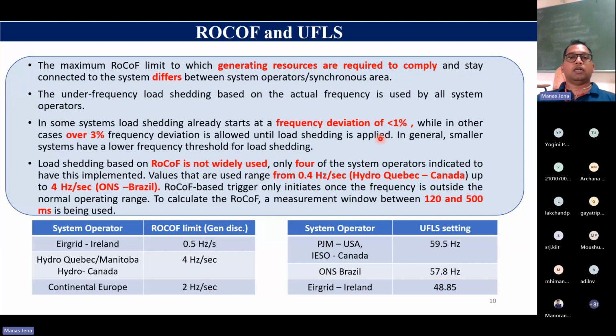Similarly, under frequency load shedding: that means frequency is going down, you have more load than generation, so you shed some loads so that the generation balance is maintained. PJM in the USA uses 59.5 hertz. Of course, they work in stages, so there will be different stages for these thresholds, and 59.5 is the first one. Whereas in Brazil, they use 57.8. Ireland uses 48.85. So what I'm trying to convey is that different operators use different ROCOF and UFLS thresholds for their protection schemes.